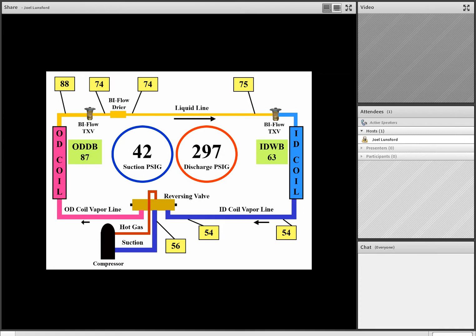87 degrees outside, 63 degrees inside. As we take a look at the refrigeration cycle, we see that all of the temperature blocks have been activated. We see we've got 54 degrees across the indoor coil vapor line, and we have a 2 degree temperature rise across the reversing valve from 54 to 56, which is normal.